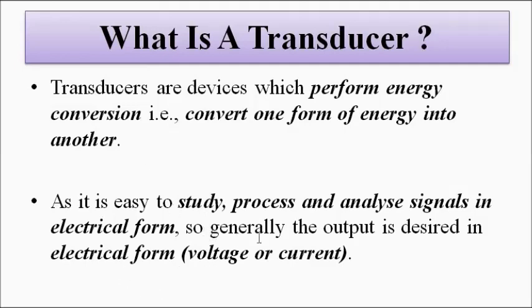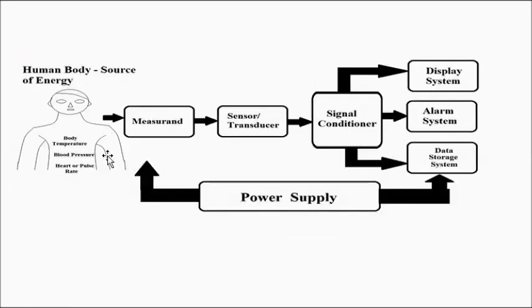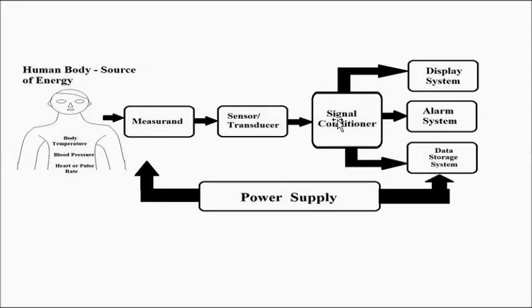The output is in voltage or current form so that it is easier to process, study, analyze, and use for diagnostic purposes. This is the layout of a basic biomedical measurement system. We have the body parameters to be measured — body temperature, pressure, heart rate, pulse rate, respiration rate, blood flow rate, anything. It is measured with suitably placed transducers and sensors. The output of the sensor or transducer is given to the signal conditioner block, which performs amplification, filtering of noise, frequency response adjustment, providing power to passive transducers, and linearization of the output.